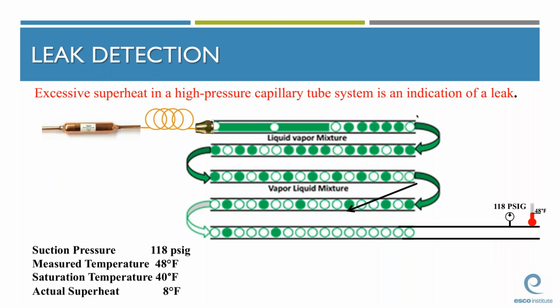On systems equipped with capillary tubes or fixed bore metering devices, superheat calculations are used to determine if an evaporator is operated with an excess or deficiency of refrigerant. Excessive evaporator superheat in a cap tube system is an indication of a leak. Be sure to provide your students with some examples of superheat calculations as well as some other causes for high evaporator superheat. Because as we know, a refrigerant leak is not the only cause for high evaporator superheat.